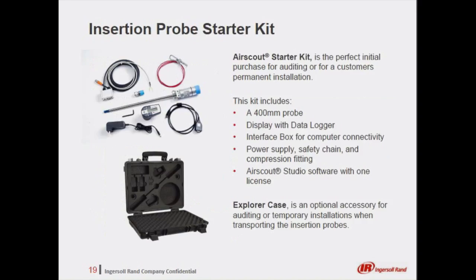The Airscout Starter Kit is the perfect initial purchase for auditing or a customer's permanent installation. The kit includes a 400 mm probe, the display with data logger, power supply, safety chain, and compression fitting. It also includes a license key for the Airscout Studio, as well as the interface box for connectivity of the probe into the computer. Other recommended parts to install the flow meter are a saddle clamp and a 1/2 inch male to female ball valve.